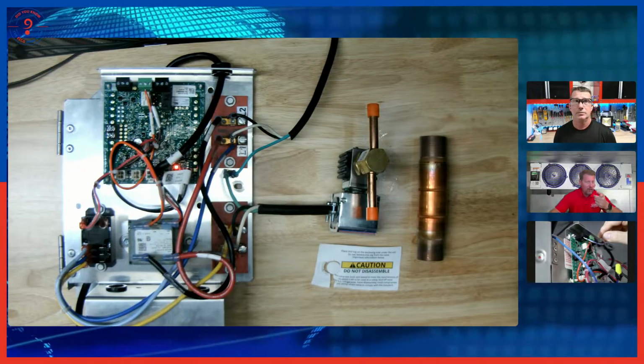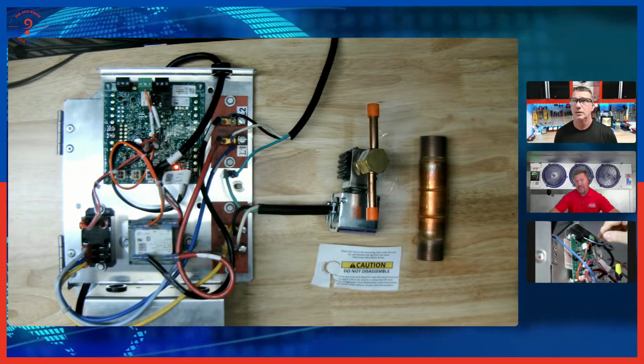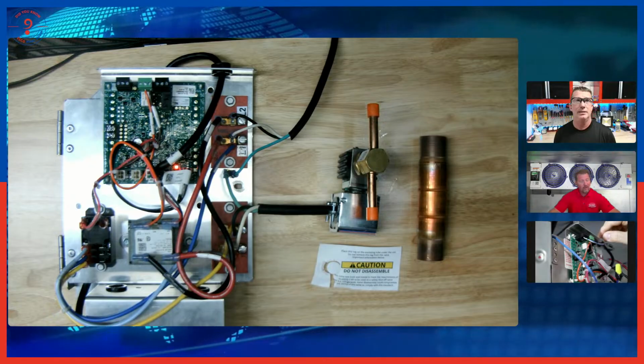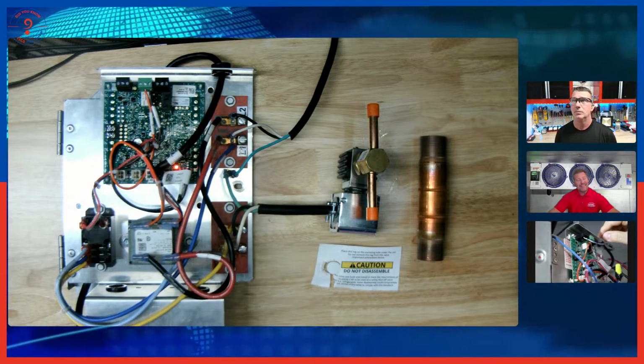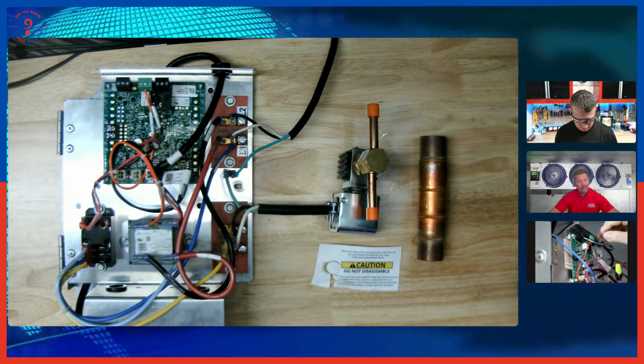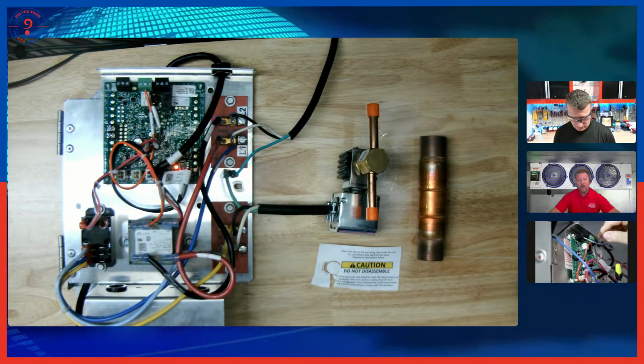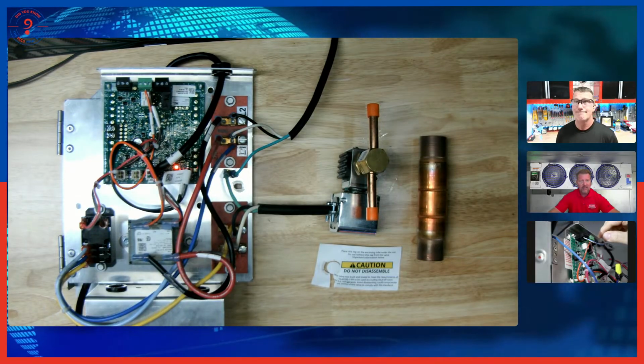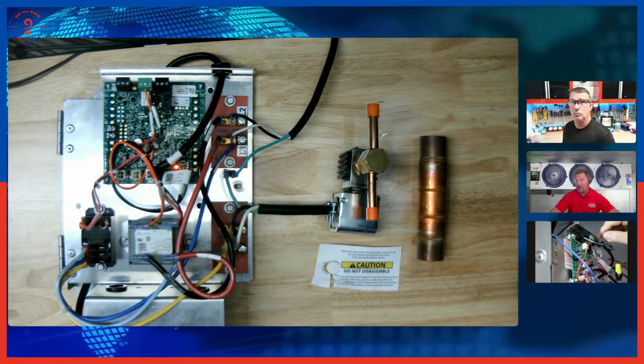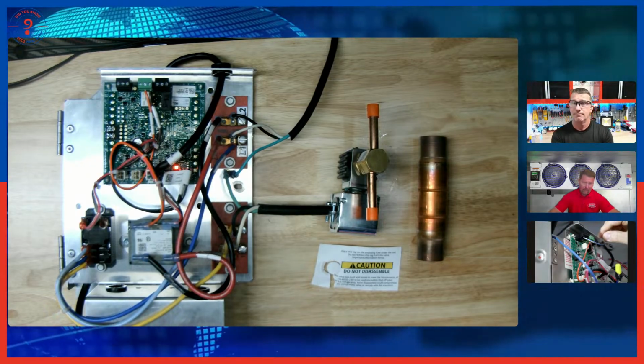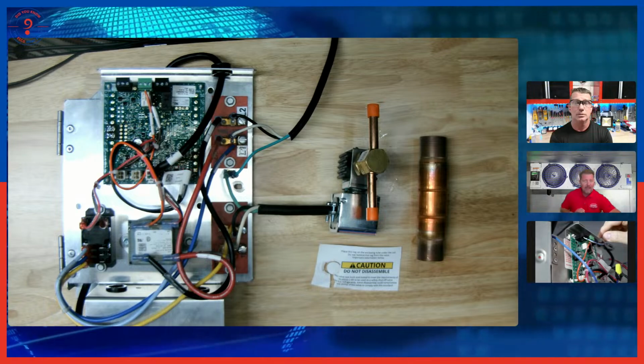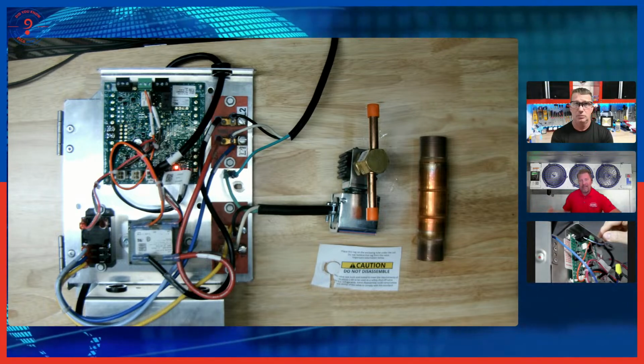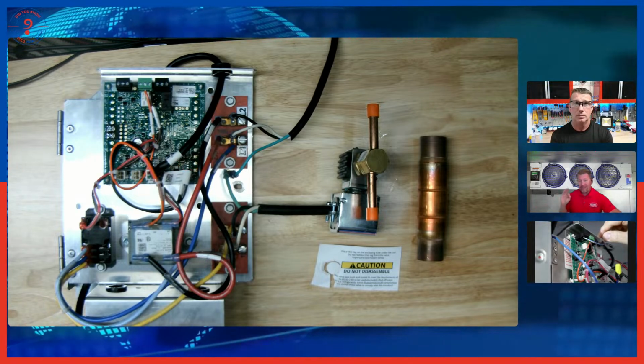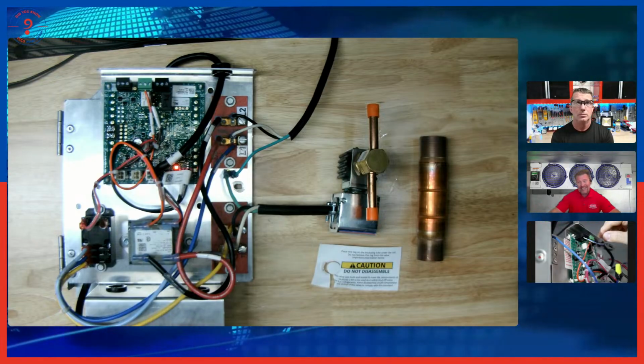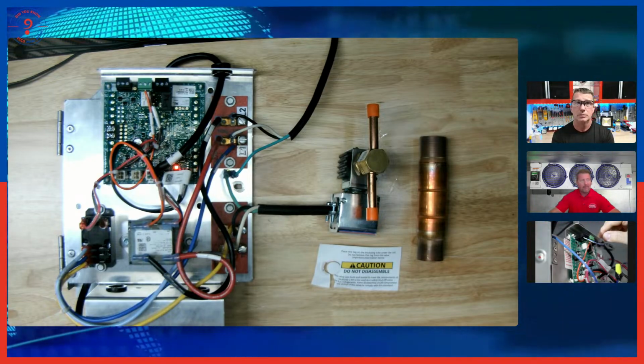Now, I will say you're blinking red right now. This is still initializing. Okay. So there is a 5-minute initialization from power up where this controller goes through a self diagnostic, and basically I don't know if it calibrates itself. Again, I'm not a control specialist. But it is calibrating and initializing. So when that's final, you will see a green light. And that normally takes about 5 minutes.